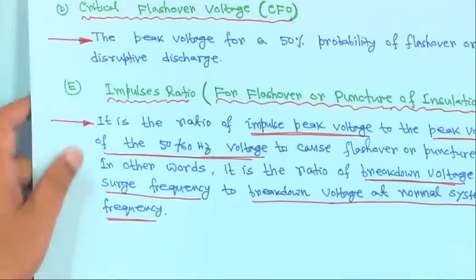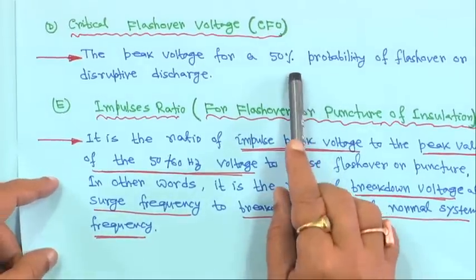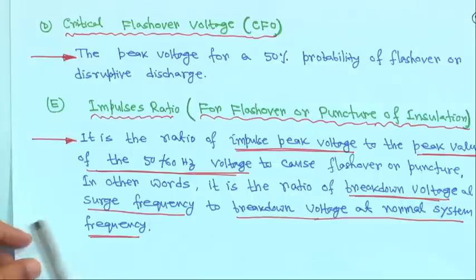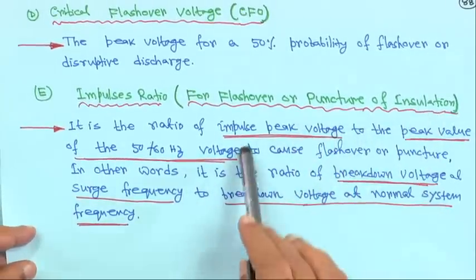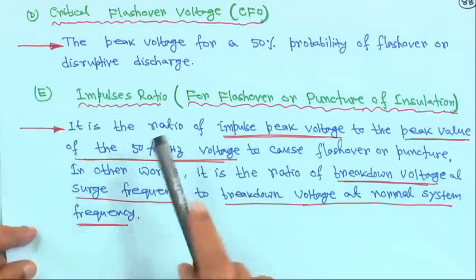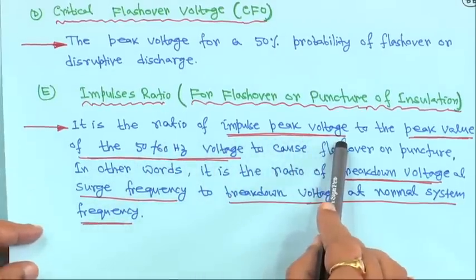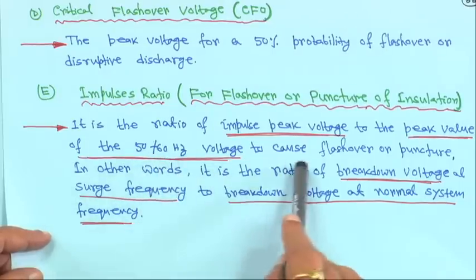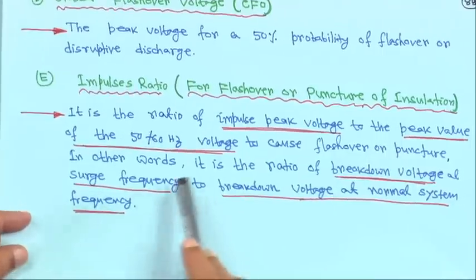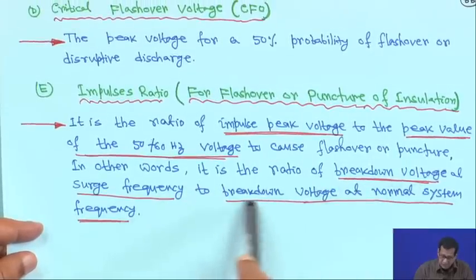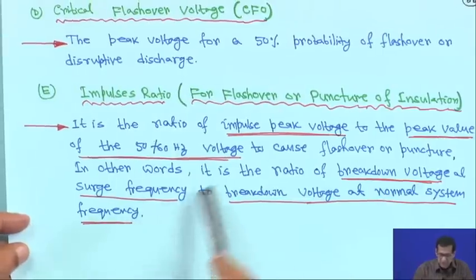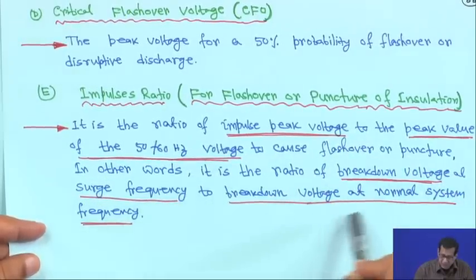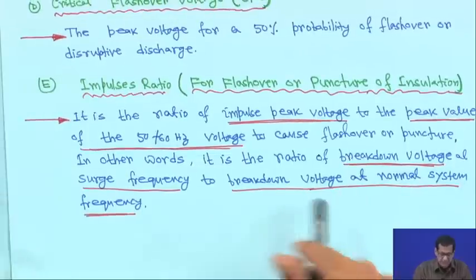The Critical Flashover Voltage, or CFO, is the peak voltage for a 50 percent probability of flashover or disruptive discharge. The impulse ratio for flashover or puncture of insulation is the ratio of the impulse peak voltage to the peak value of the 50 or 60 Hz voltage that causes flashover — in other words, the ratio of breakdown voltage at surge frequency to breakdown voltage at normal system frequency.